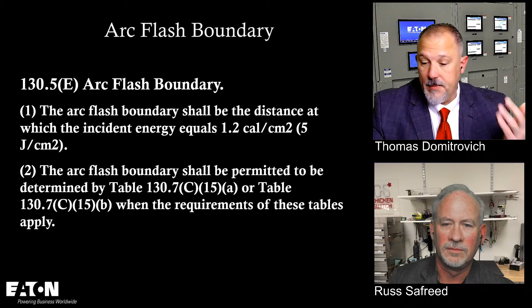And for the most part, what you and I are familiar with is the cases where those arc flash boundaries exceed the restricted and prohibited approach boundaries, and that's where you're really going to see the value of getting out of in front of the equipment. Medium voltage applications, 480, 600 volt applications. Those are the areas where you say, listen, I'm going to get out in front of that piece of equipment.